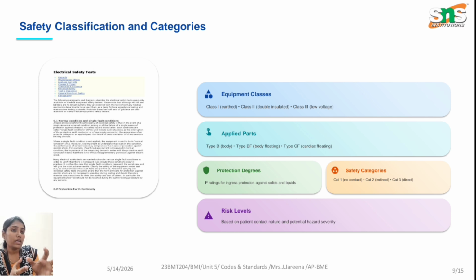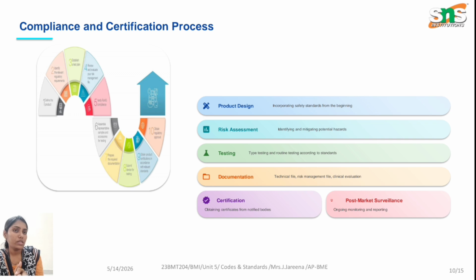The highest risk and strictest regulation has to be followed in the case of cardiac floating, because these types of applied parts have direct contact with the heart. Even a minute leakage current will affect the heart. That is the reason type CF has very strict rules compared to type B and type BF. Based on severity and type, whether invasive or non-invasive, based on the contact type of the device, the codes and standards will differ from device to device. Compliance and certification, we already know.